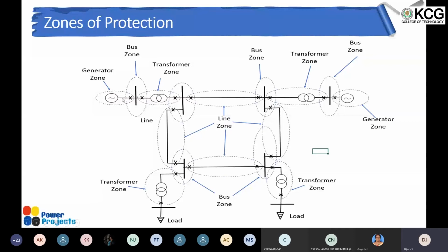For that, we need to understand zones of protection. For generators, there will be a generator zone of protection, and for the bus bar, a bus zone of protection. Similarly for transformers and another bus bar, and these are the lines, so a line protection zone will be here. I'll show the laser. Here the line protection zone will be there, and again a bus bar, transformer or generator protection zone. Like that it goes on.